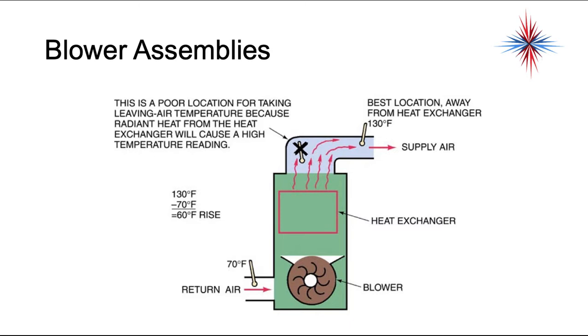If the temperature rise is too high, you need to increase the airflow. If the temperature rise is too low, you need to decrease the airflow. The reason for this is the longer the air stays in the heat exchanger, the hotter it's going to get. So if you increase the speed of the blower, you're going to cool off the air that comes out the supply duct. This works only if your ductwork is set up for the difference in airflow volume. Don't decrease it too much because you still have to move air across the heat exchanger. Temperature rise tells you a lot about what the airflow is doing.